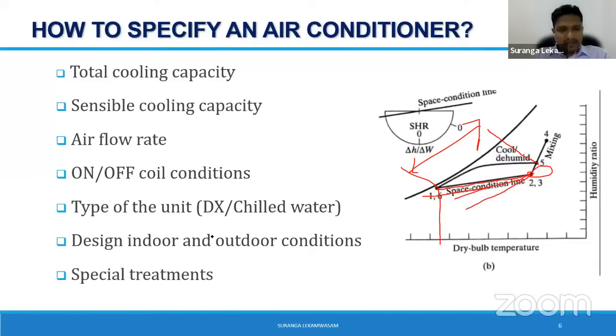Then in addition to that, you need to specify whether you need a DX coil or a chilled water coil. What is the system that you are going to install? Design conditions: what is the indoor temperature, the outdoor temperature? That you need to specify, right? Because if you are running the AC at 20 degrees versus 26 degrees, there is an impact. So all these need to be specified.